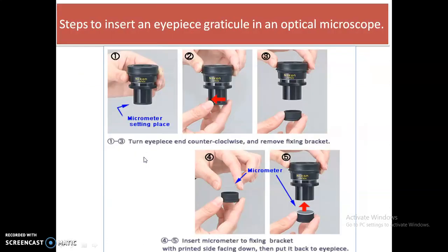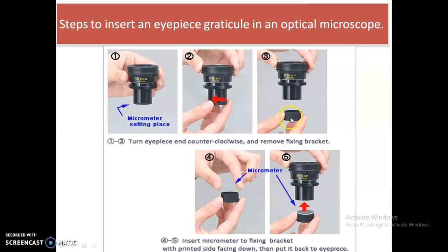First we will discuss the steps for how to insert the eyepiece graticule into the eyepiece of an optical microscope. As you can see in the stepwise images, in the very first step we will turn this particular end of the eyepiece counterclockwise and remove the fixing bracket. By removing this fixing bracket we can now place our graticule into it.